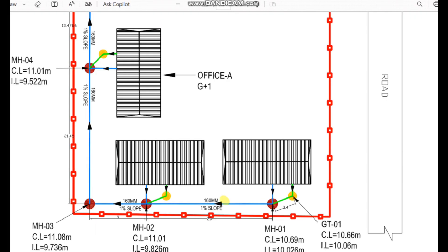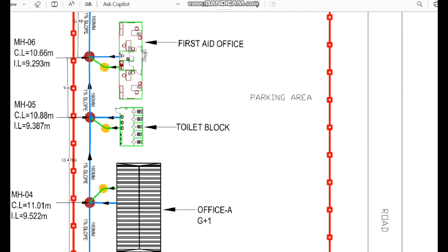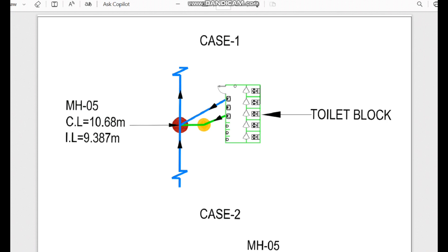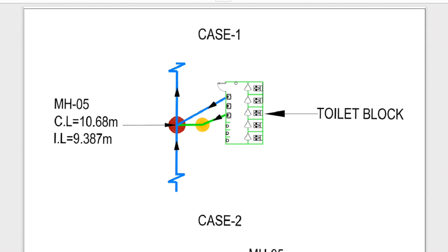I have indicated the water flow direction with arrows showing the route to the holding tank. For Case 1, I have taken the toilet block where water goes to manhole number 5. The wastewater from the wash basin goes to the gully trap, from the gully trap to the manhole, and the soil water goes directly to the manhole. However, because of one issue, this installation is not acceptable. I will continue with Case 2 and then reveal the answer.